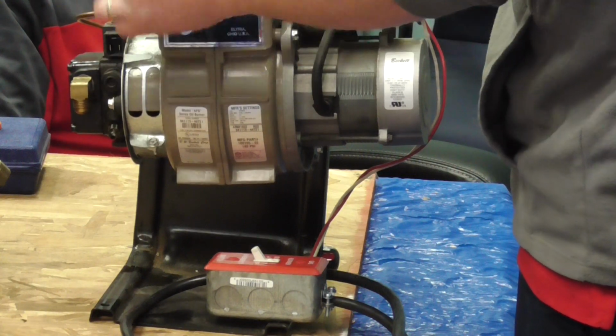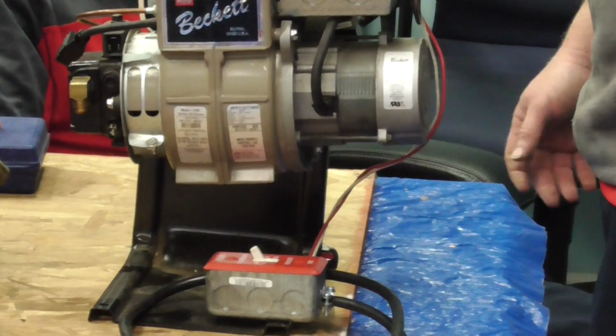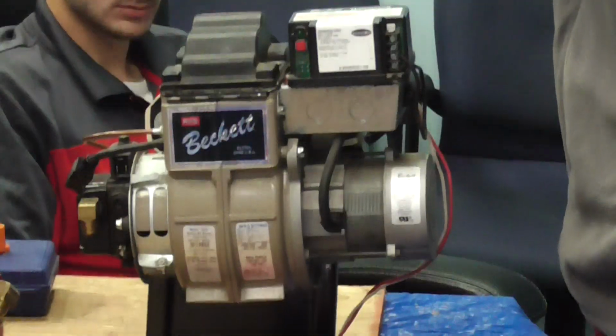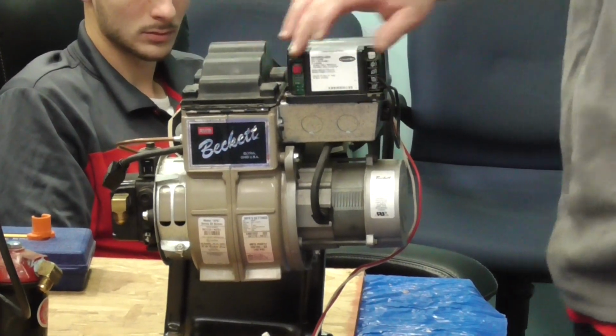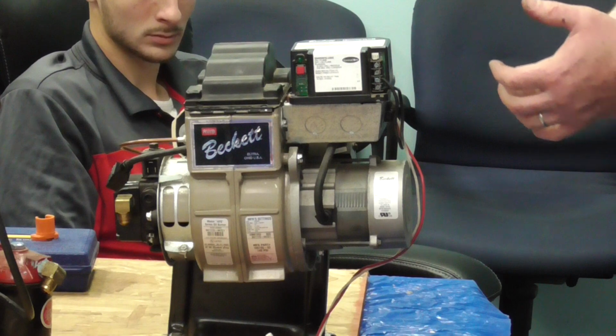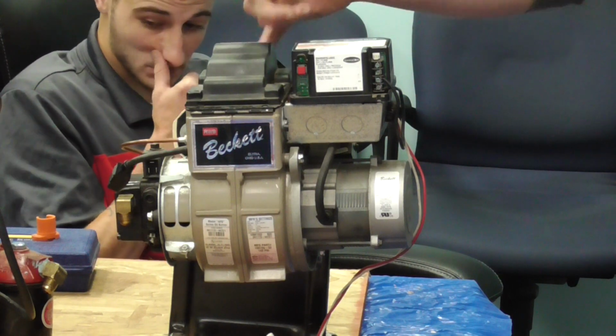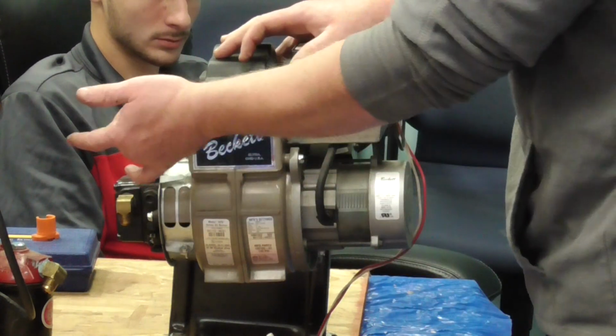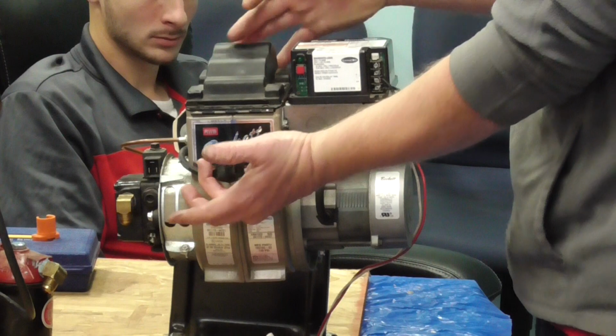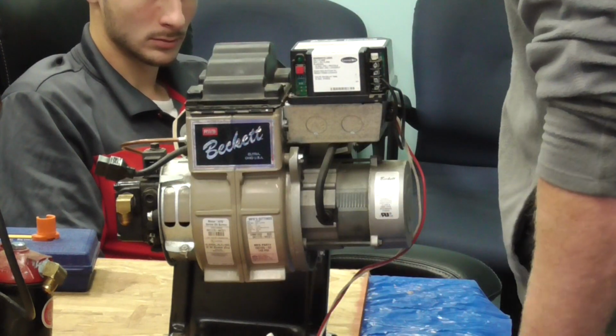You can unplug this thing, get your oil flowing nice. Once you get your oil flowing nice, then you can plug it back in. Because some have a priming mode. I don't know if this one has a priming mode offhand. The other ones do, or run for, I think it's 4 minutes, and it'll just run the pump without hitting the igniter or anything else, and ignore the flame sensor. But if you just unplug this thing, you won't keep spraying oil in as it's trying to fire.